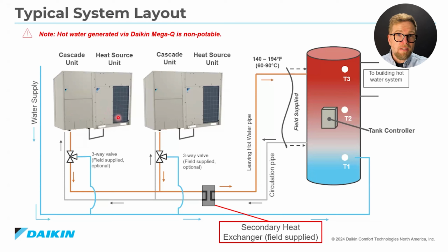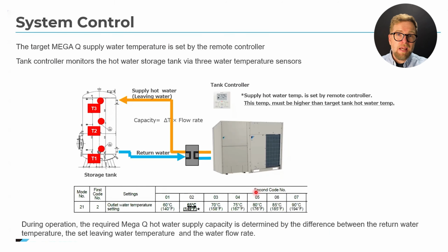The cascade unit is equipped with its own compressors that boost the temperature of the R134A even further. From there, a built-in heat exchanger uses the R134A to heat the water you're sending to your storage tank or your secondary heat exchanger. Essentially, it's a step-up system. The first loop raises the temperature and the second loop raises it even higher, up to 194 degrees in some scenarios. The key element here is the tank controller kit.